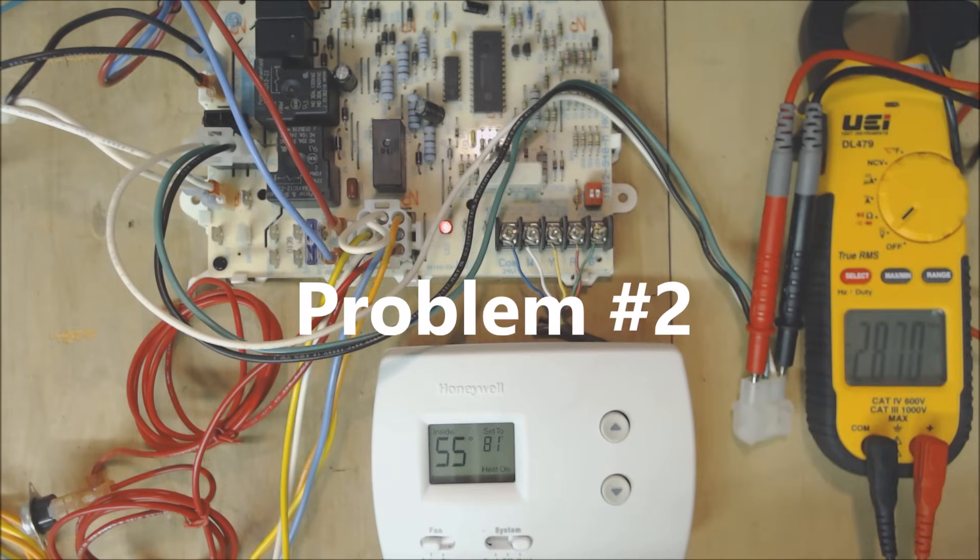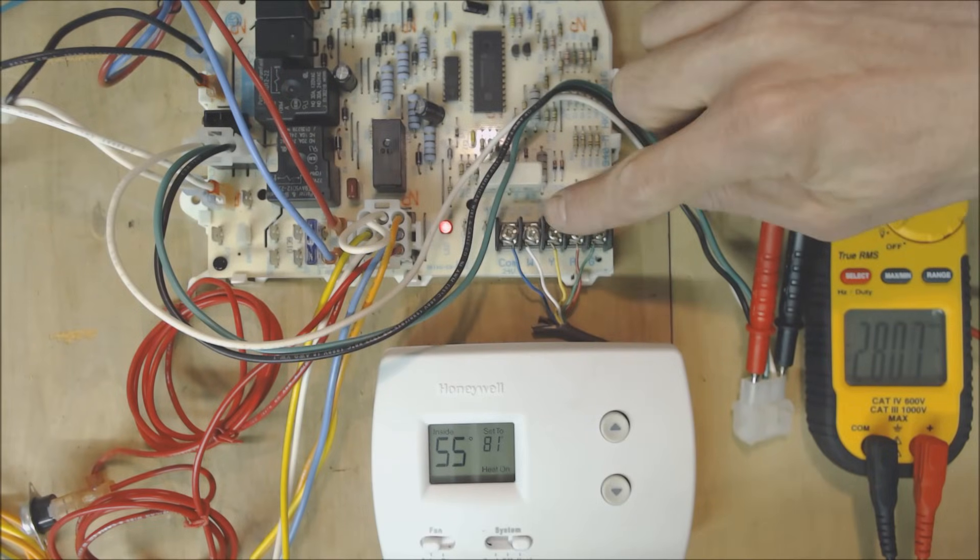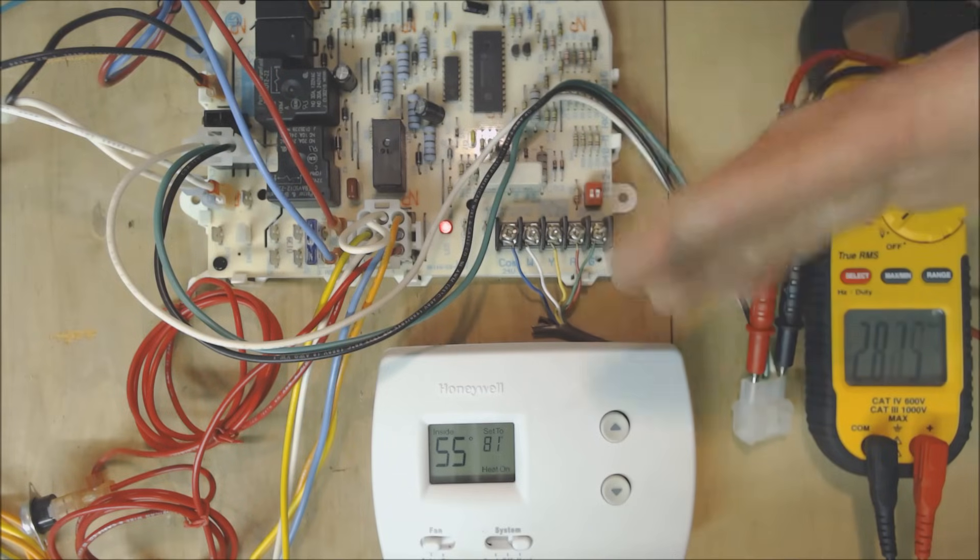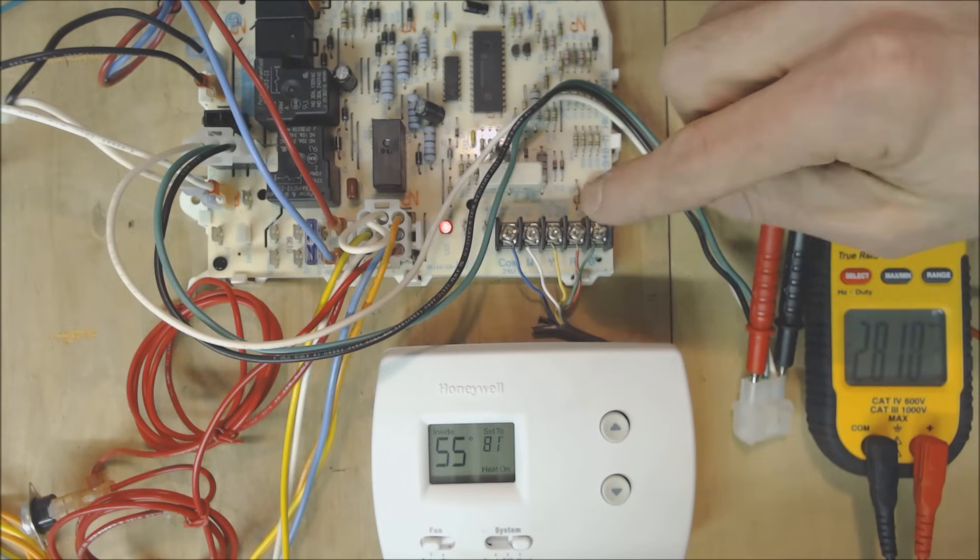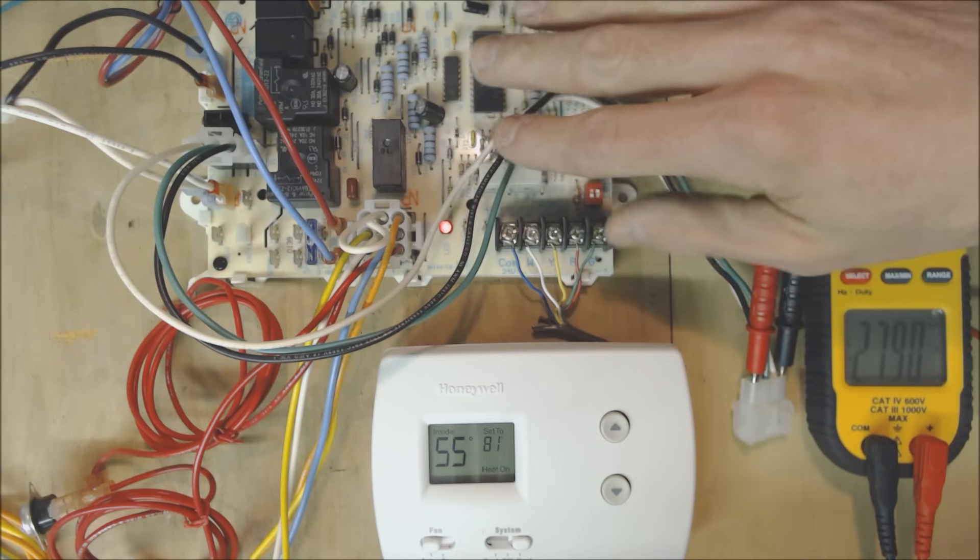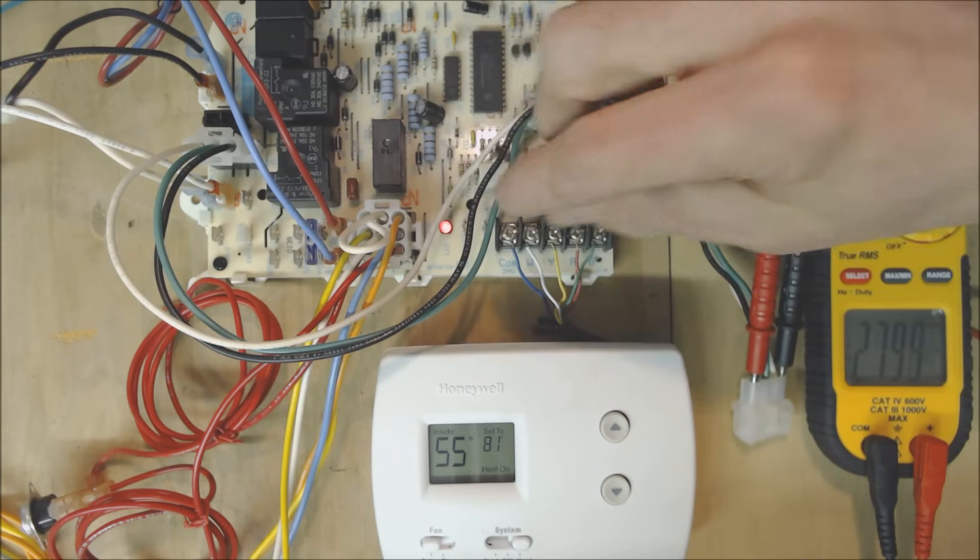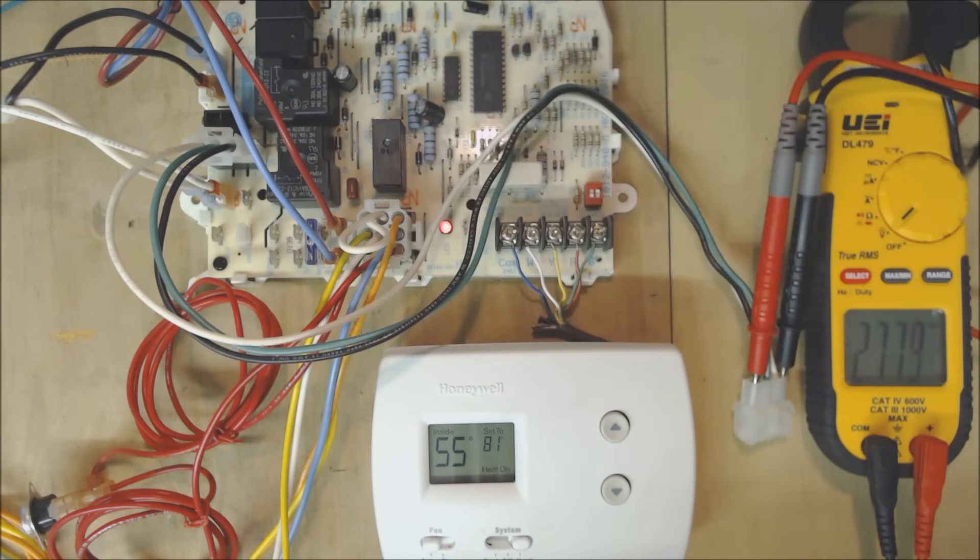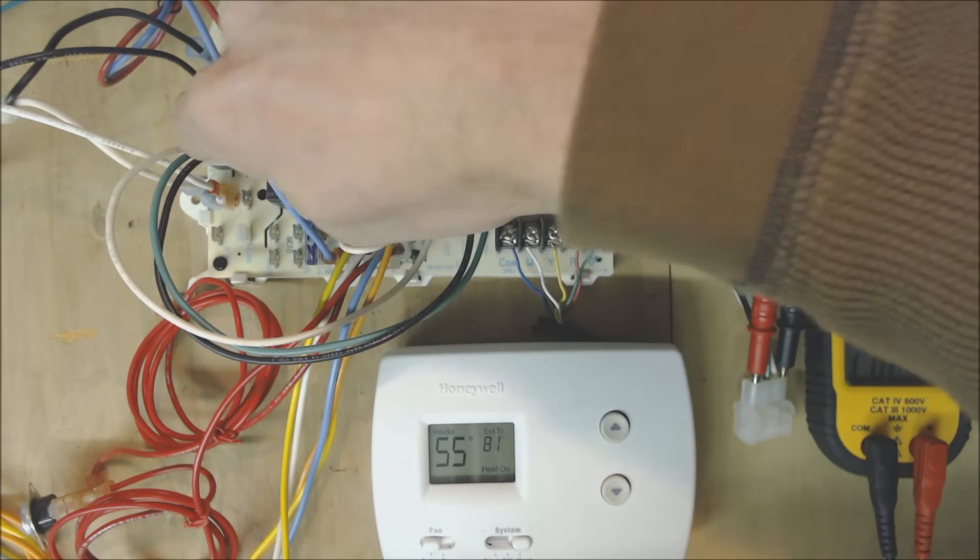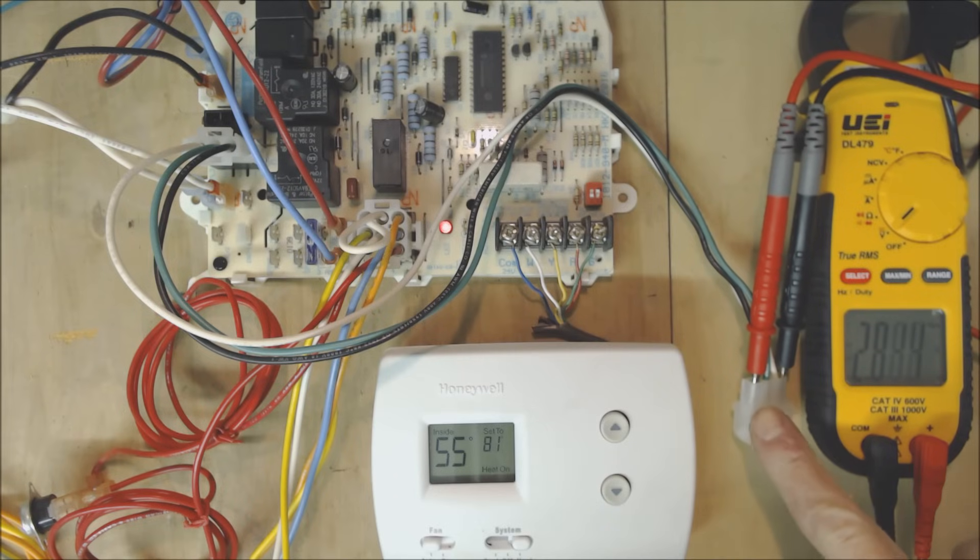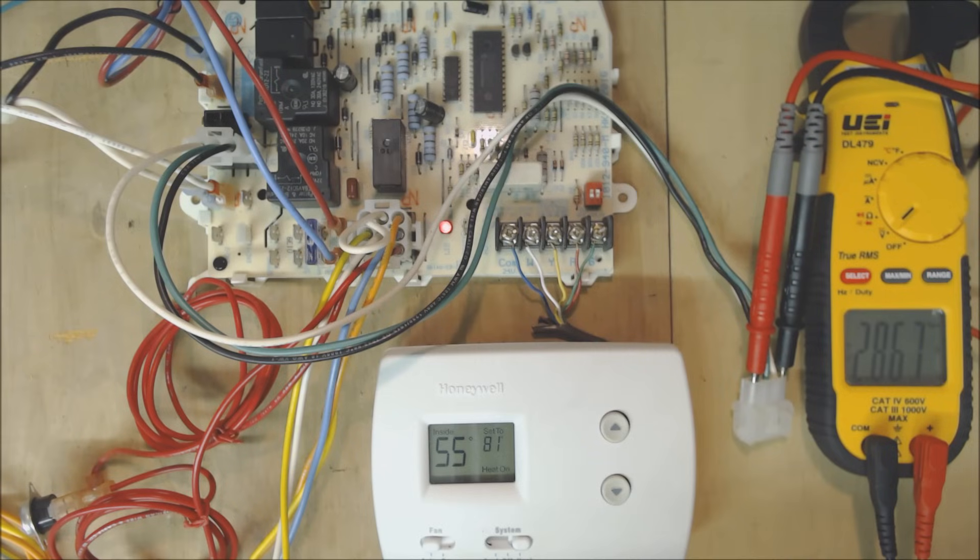So this is problem number two. Once you've verified that you have 24 volts from W to C and actually it's anywhere from 24 to 29 volts. So once you've verified that you have a signal calling for heat you want to go ahead and check for your inducer motor wiring. You want to make sure that you are finding the right wires here and you're following it from the inducer motor back to the control board. In this case I've already disconnected the wire and I have the probes in and I'm checking for voltage. So you see that the control board is not sending the 120 volts that it needs to the inducer motor. So in this case this would actually be a board problem.